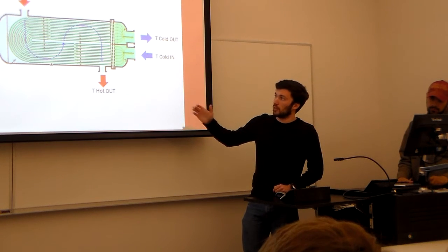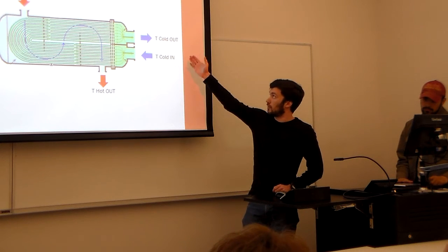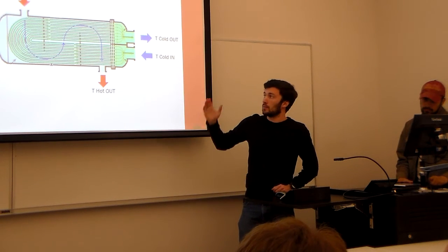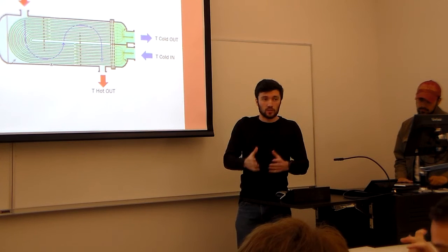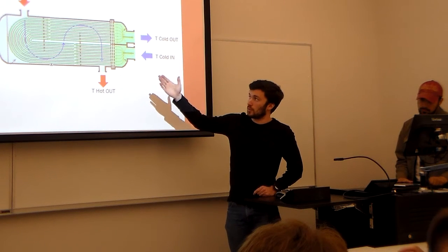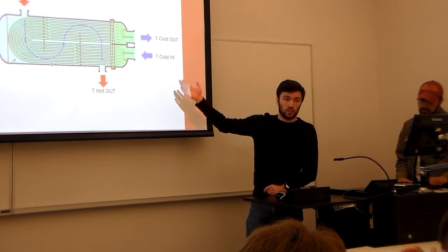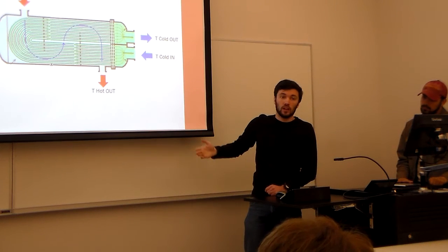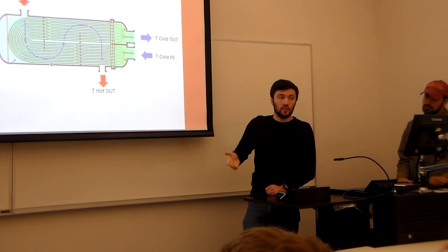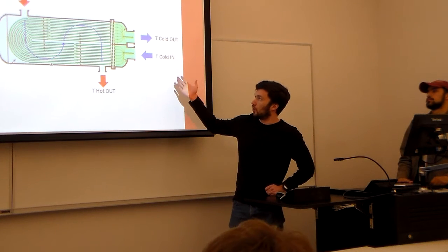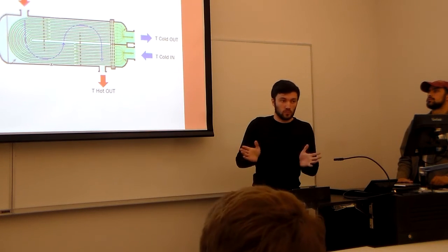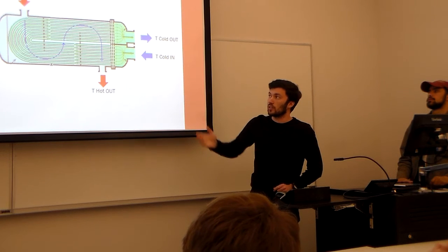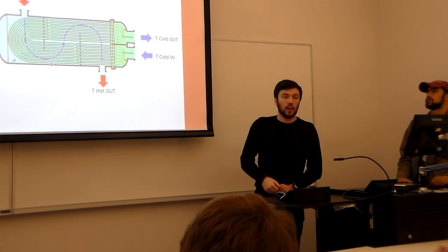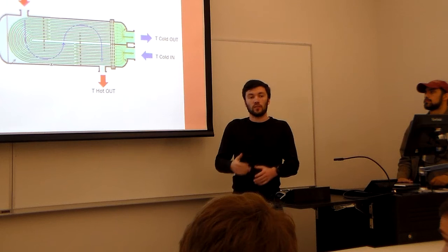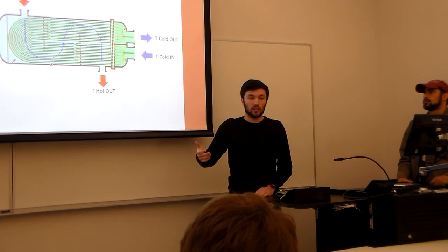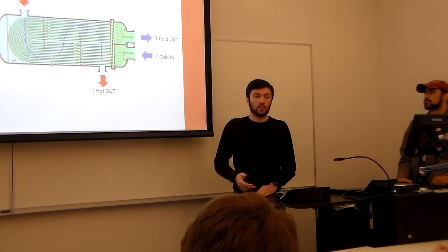And when they went back through the data logs, they realized that this outlet temperature was low. And doing a very generalized heat transfer look at it, you can see that the outlet temperature depends on the inlet temperature, the heat transfer to the cold water, the mass flow, and CP. The inlet temperature wasn't changing, and the mass flow in the cold side, through the mass sensors they had, remained constant. So they knew that there was a decrease in heat transfer to the cold fluid. And typically that happens because of a failure between the tubes and they begin to mix. So the heat transfer to the cold fluid is significantly less than before.